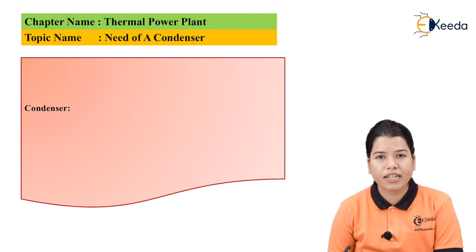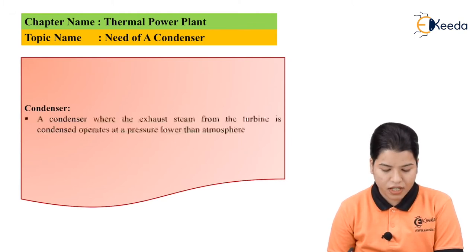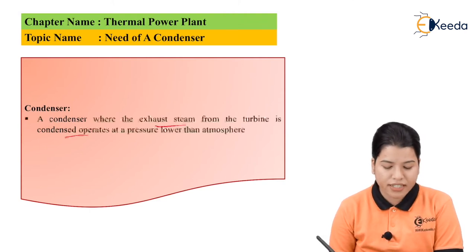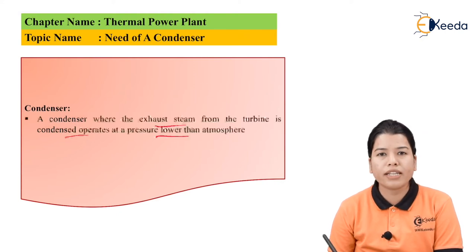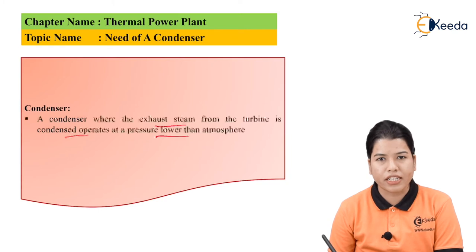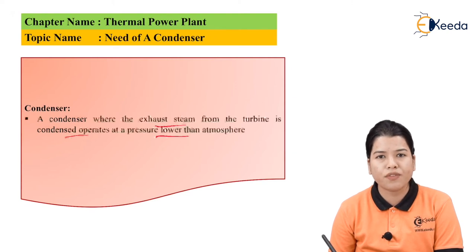The condenser is where the exhaust steam from the turbine is condensed, and it operates at a pressure which is lower than the atmospheric pressure. The output of the steam turbine is coupled with the generator, so the mechanical energy gets converted into electrical energy. Whatever steam is let out from the turbine has to get condensed, so the condenser is used for the condensation of steam at a pressure lower than atmospheric.